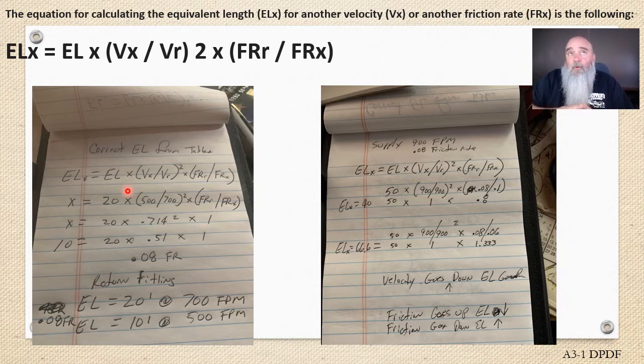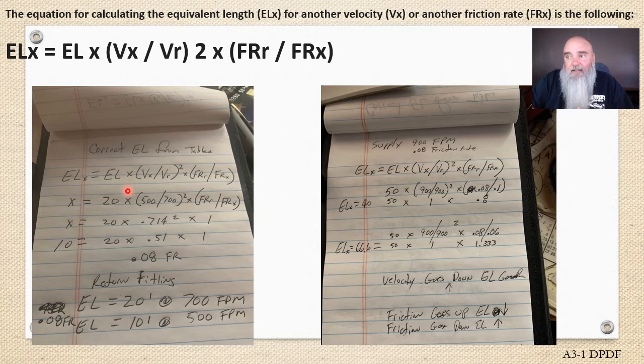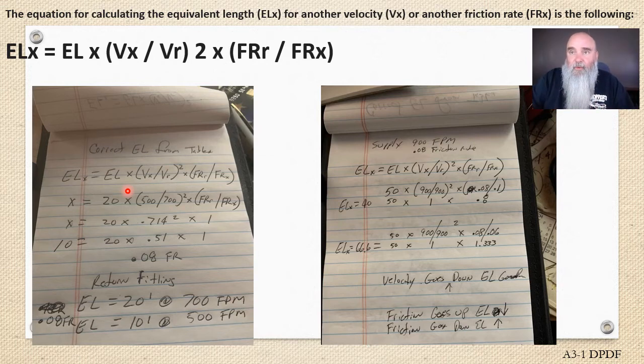What happens in reality far too frequently is we shove too much air through too small of a duct, and that increases the pressure drop or equivalent length of our fitting. And that ends up with higher than anticipated static pressure, which generally ends up with a duct system that doesn't move the air that we need it to. Where if it does, you've got to turn the TV up every time the system comes on because smaller duct...